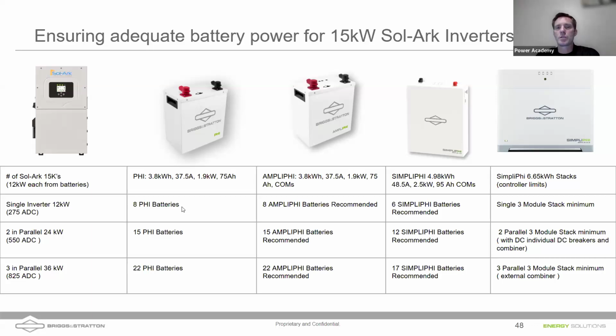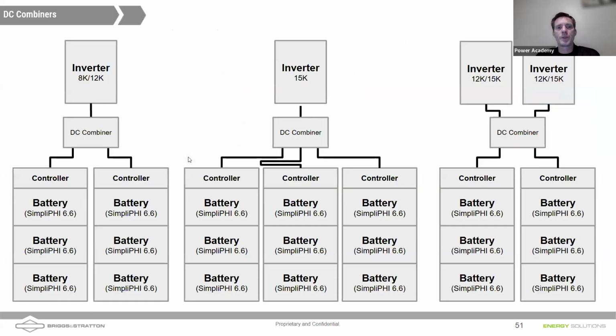to power that inverter. Keep in mind, this inverter can surge. It can pull 24 kilowatts for a short time, and we want to make sure that the battery bank is big enough that it won't be damaged when the inverter's drawing it. Also want to point out that with a single 15K, you could do 2 stacks and combine on the inverter. But if you're using other inverters like the 8K or the 12K and you've got multiple stacks of batteries, you'll want to use a DC combiner and then bring that single combined stack into the inverter.